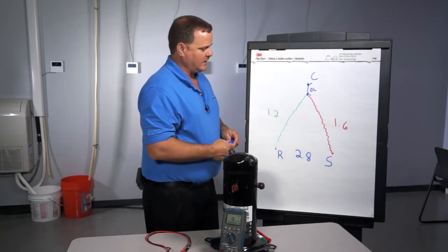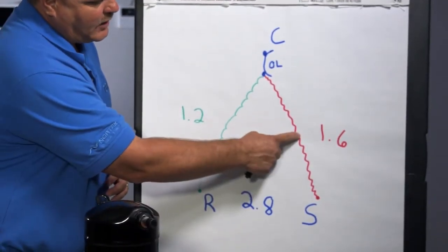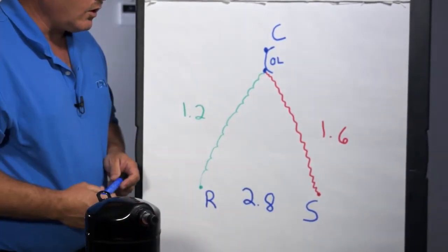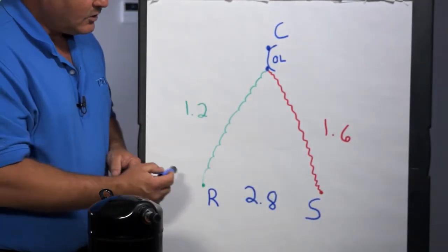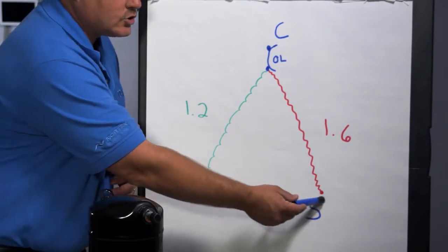If I had an open start winding, you'd have a winding break in the middle of the winding, so you would no longer get a reading from start to common, and you'd no longer get a reading from run to start.